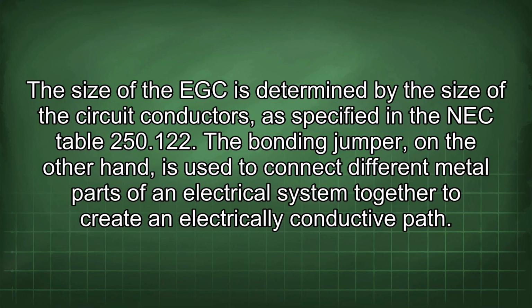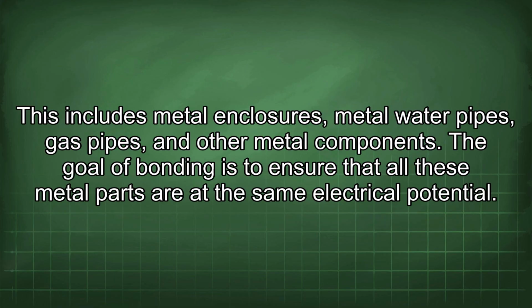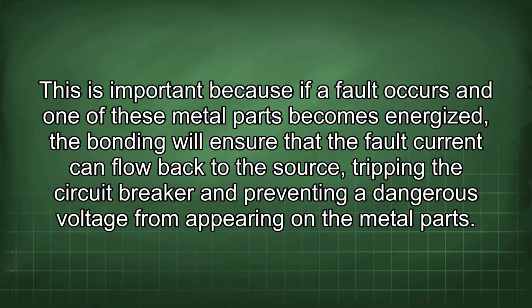The size of the EGC is determined by the size of the circuit conductors, as specified in the NEC Table 250.122. The bonding jumper, on the other hand, is used to connect different metal parts of an electrical system together to create an electrically conductive path. This includes metal enclosures, metal water pipes, gas pipes, and other metal components. The goal of bonding is to ensure that all these metal parts are at the same electrical potential. This is important because if a fault occurs and one of these metal parts becomes energized, the bonding will ensure that the fault current can flow back to the source, tripping the circuit breaker and preventing a dangerous voltage from appearing on the metal parts.